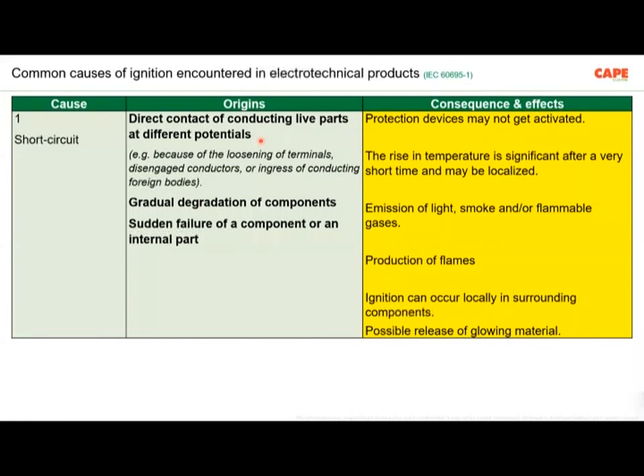The second problem is gradual degradation of the components. That means the devices used in your equipment, such as capacitors or MOVs or diodes, if they degrade, or in a wound transformer or a small instrument transformer, if the winding insulation fails, of course, it can also create a short circuit. The third part is the sudden failure of a component in the internal part of an equipment. These three are the recognized origins of short circuit, and now the consequences or the effect.